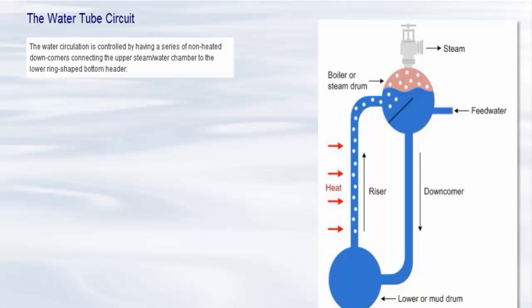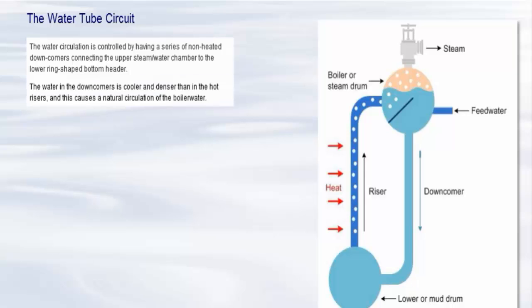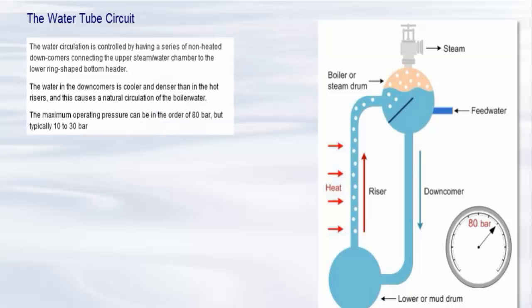Inside a water tube boiler, the water circulation is controlled by having a series of non-heated downcomers connecting the upper steam water chamber to the lower ring-shaped bottom header. The water in the downcomers is cooler and denser than in the hot risers and this causes a natural circulation of the boiler water. The maximum operating pressure can be in the order of 80 bar but is typically 10 to 30 bar.